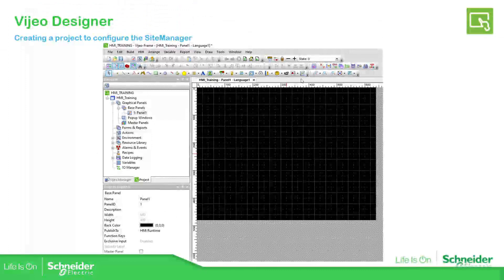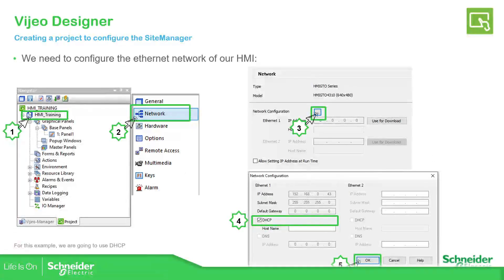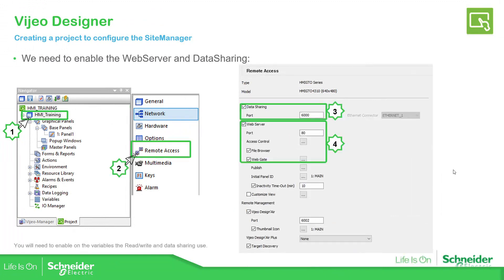This will be the application that you have. There are a few things we need to check first. In this example I'm going to use DHCP to automatically assign an IP address on the network. We need to go to HMI target, then network configuration, and select DHCP. If you want remote access for the web gate, go to remote access, enable data sharing, and select for each variable the data sharing, read/write of the variables, the web server, and the web gate.